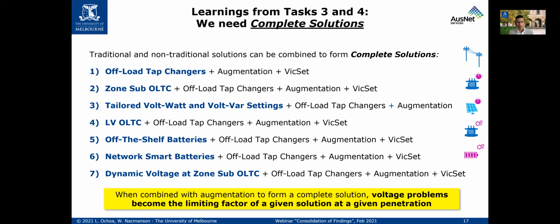The first is off-load tap changers plus augmentation plus the Victorian settings. Changing the tap position has a cost, since you need to disconnect the transformer and use a genset to keep powering those houses. But once implemented, this is something DNSPs are doing across Australia and the world, and using this existing technology is very effective in most cases, though it has limitations. Still, it's a good solution.